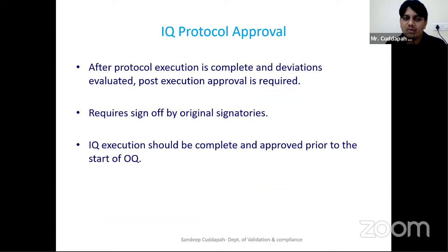So finally, once the IQ protocol is approved, you will execute the protocol. If any process or anything is deviating and not meeting requirements, you will initiate a deviation. In the deviation you will investigate what actually caused that failure, and take steps either to rectify or to modify that. You will give corrective and preventive actions as part of the deviations. Based on that, your further qualifications will be continued.